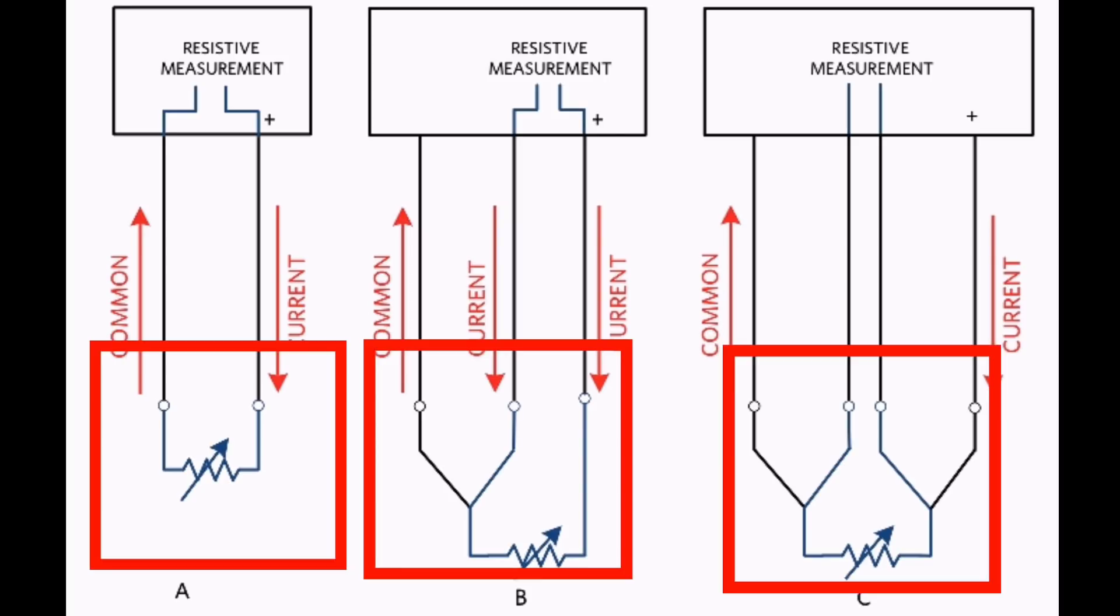The four wire configuration is most accurate. Sense and force leads eliminate the effect of wire resistance, meaning you don't have to worry about the wire length.